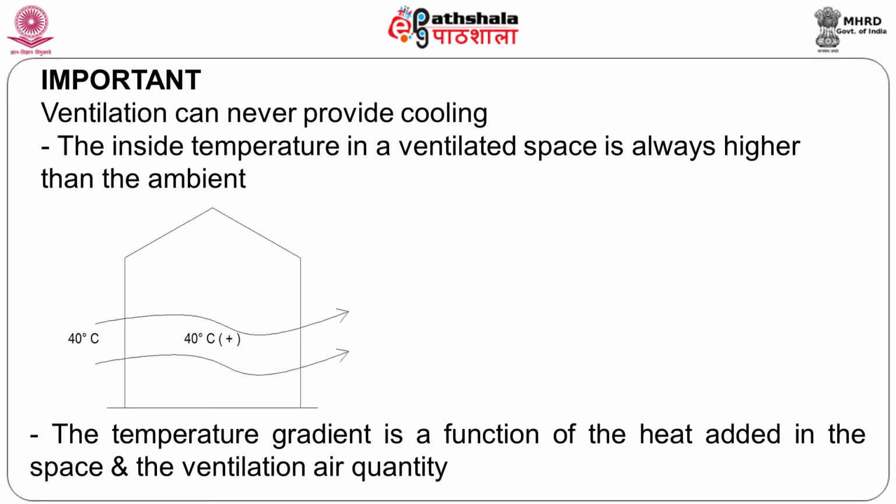Now, among all this talk of 1 air change, 2 air changes, 20 air changes, 10 air changes, there is one aspect which must always be remembered: ventilation can never cool. I am talking of, again, an ambient from where I am addressing this session, hot and humid.